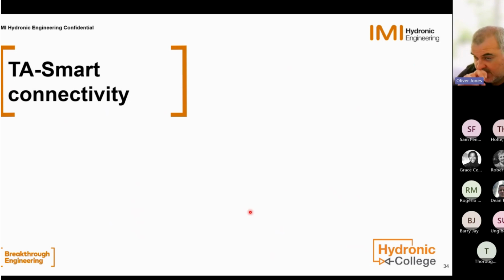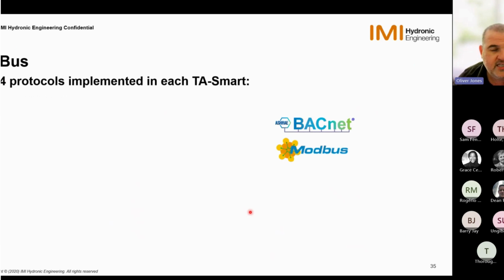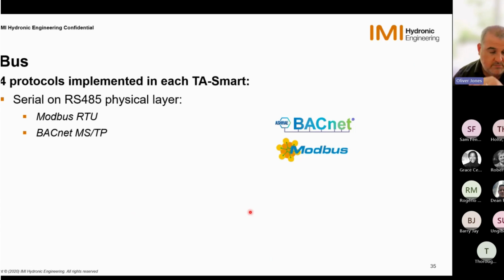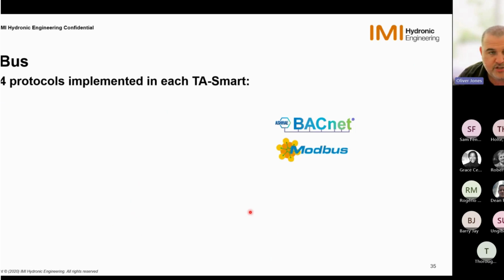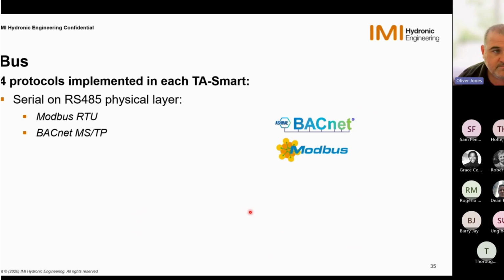So just again, a brief touch on the TA Smart connectivity. So from bus, we have 4 bus protocols which are implemented on every TA Smart. So that means we don't have a version for BACnet or a version for Modbus or a version for IP over RS485. All of these options are available and wired into and configured into the Smart valve itself. So we have the serial on our RS485, which is our physical layer. So this is our 3-core cable, which is doing our Modbus RTU and BACnet MSTP.